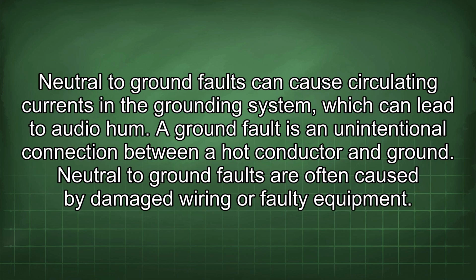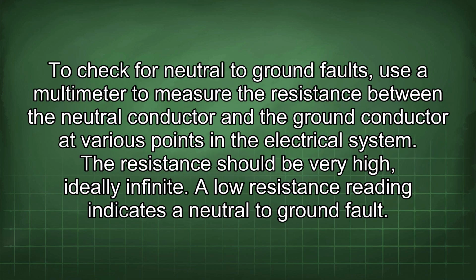Neutral to ground faults can cause circulating currents in the grounding system, which can lead to audio hum. A ground fault is an unintentional connection between a hot conductor and ground. Neutral to ground faults are often caused by damaged wiring or faulty equipment. To check for neutral to ground faults, use a multimeter to measure the resistance between the neutral conductor and the ground conductor at various points in the electrical system. The resistance should be very high, ideally infinite. A low resistance reading indicates a neutral to ground fault.